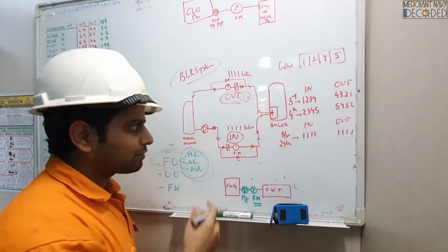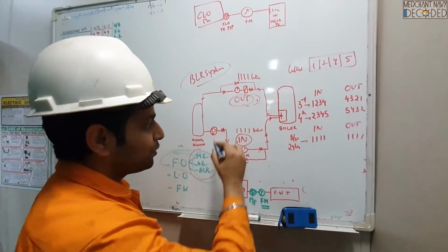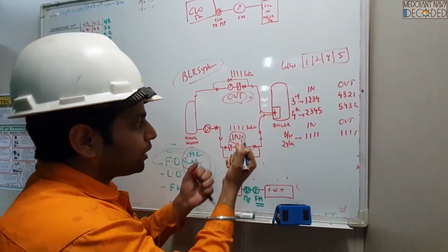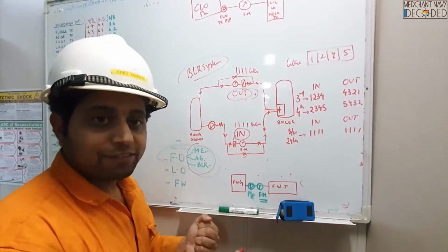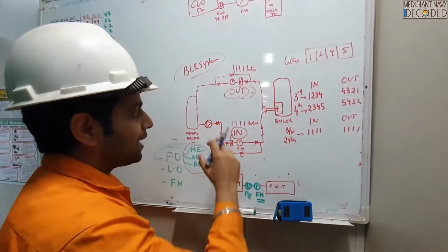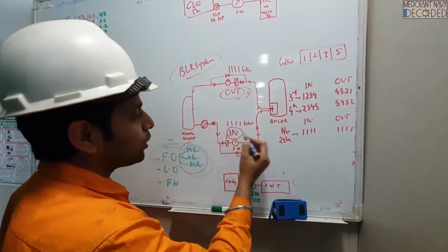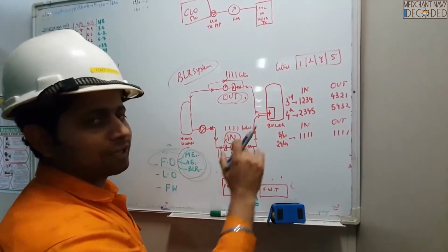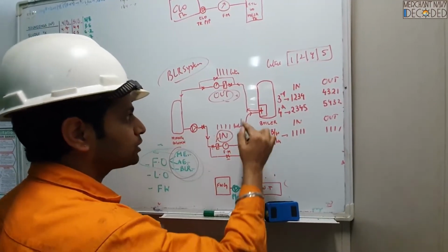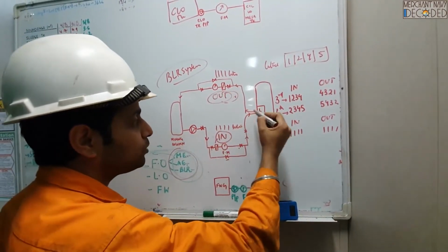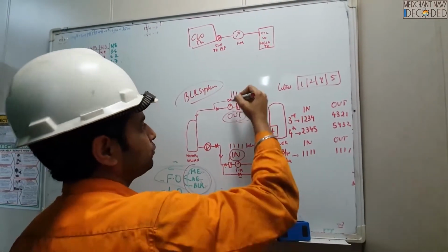Now your question might be, sir, why do we need to run the pump? Guys, this is fuel oil. If you do not circulate it, the fuel oil will choke the lines. It has very high viscosity when it gets cold. If it had been LSMGO, MDO or gas oils, it would not have been required. We could have stopped the pump, and the lines would have been normal. But if it is heavy oil, then we want this circulation to be maintained all the time. We want these lines to be hot all the time. Got it, guys? So that is why these flow meters are important.